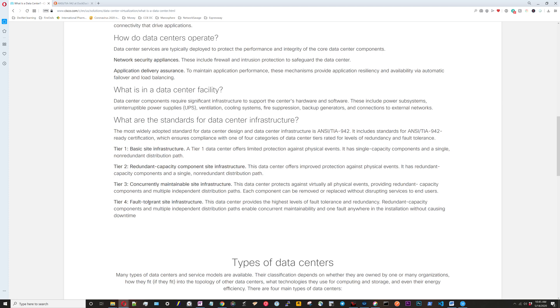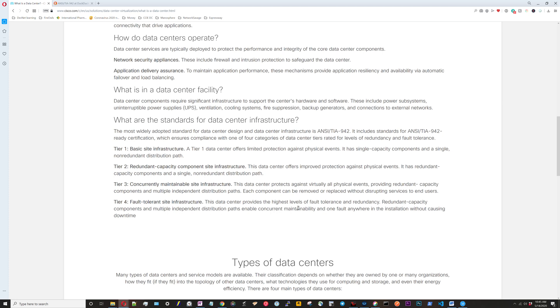A tier one data center offers limited protection against physical events. It has single capacity components and a single non-redundant distribution path. Tier four data center provides the highest level of fault tolerance and redundancy. Redundant capacity components and multiple independent distribution paths enable concurrent maintainability and one fault anywhere in installation without causing downtime.